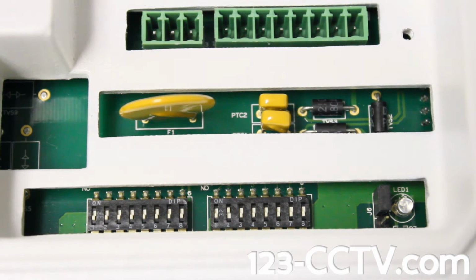Let's say, for another example, we want to adjust the baud rate settings. The baud rate dip switches are dip switches 4 and 5 on the left block. By default, the baud rate is 9600 BPS. If we want to change that BPS down to, let's say, 4800, the way that we can do that is by simply changing dip switch number 4 to on.